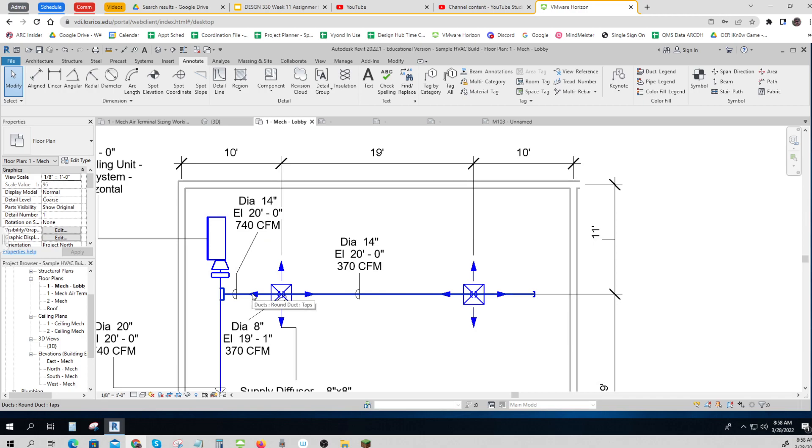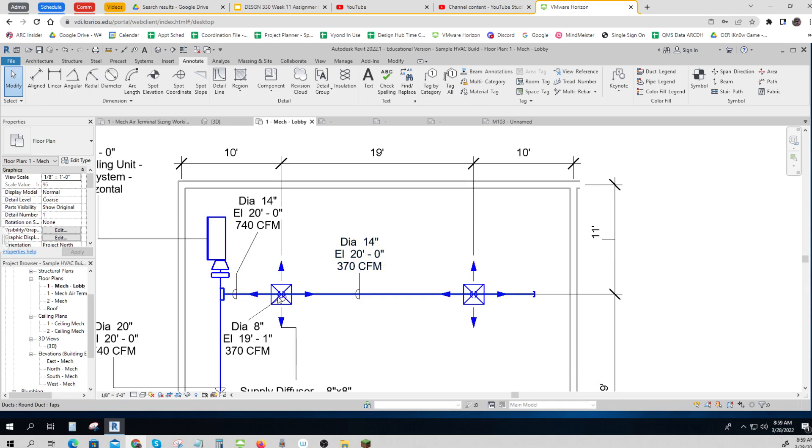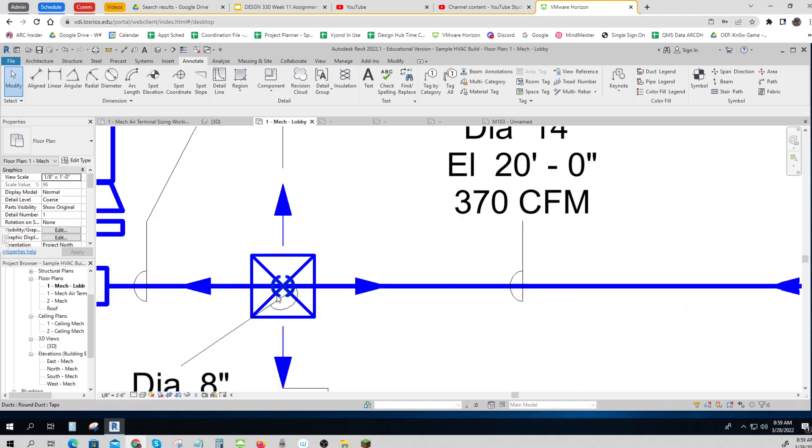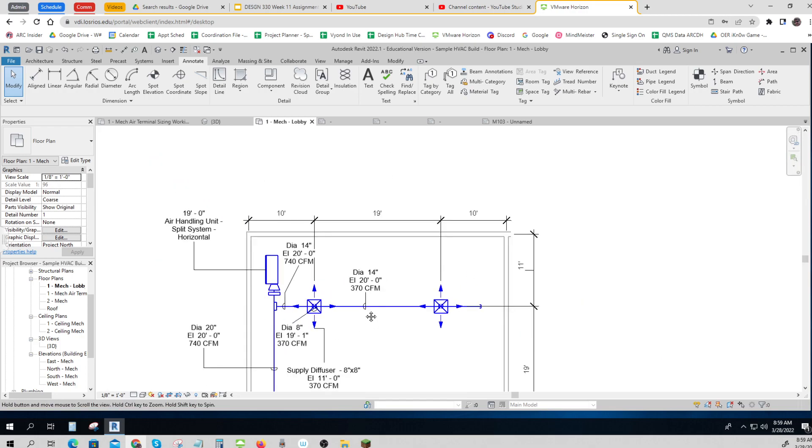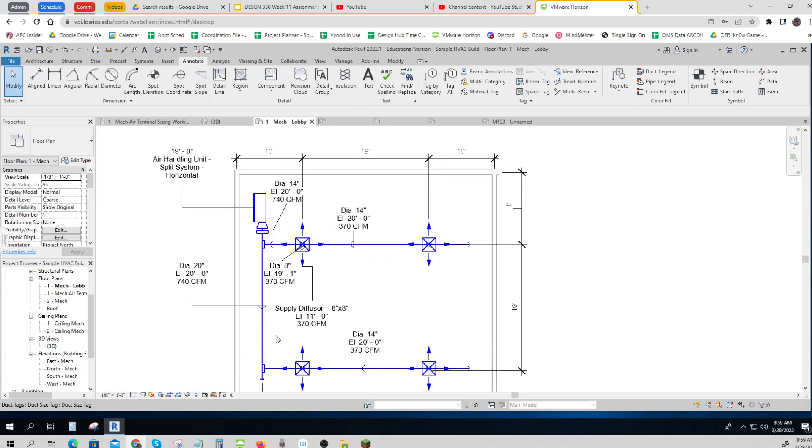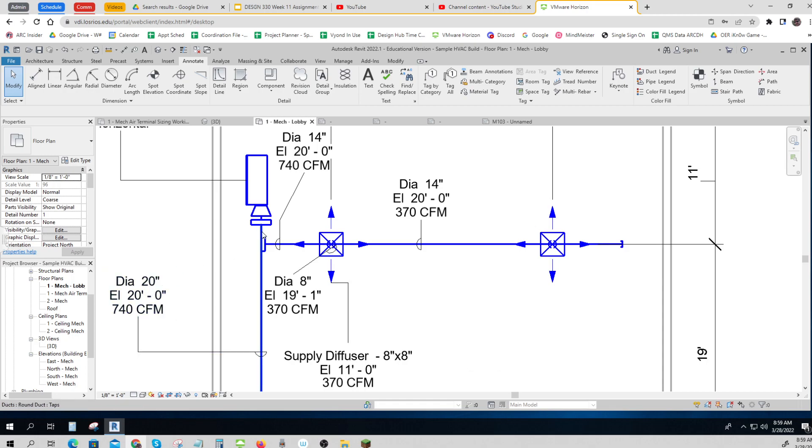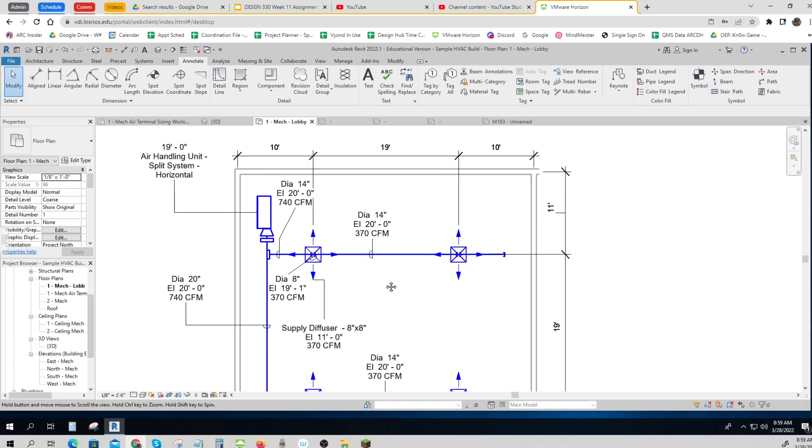Some HVAC detailers would say, well that's good for that one, but this is too big, and they might actually make you neck this one down here. It depends on what their design parameters are. And then of course I was able to pick this little piece of vertical ducting, and so I've got all of those identified. I might even put one here, shows all of the flow through there. But this is good for now.